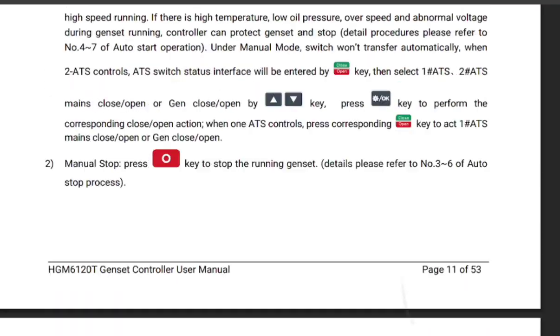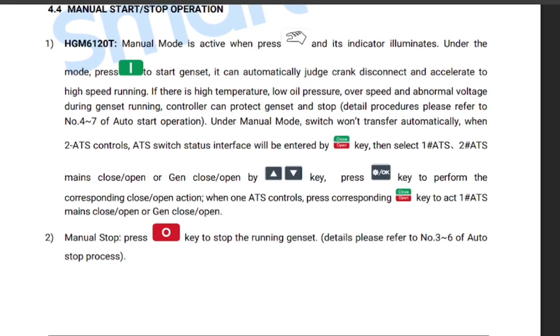So as you can see, here are some setups. As you can see, HGM 6120T manual mode is active when you press the hand key, and its indication illuminates under the mode. Press the green button, the I button, to start the genset. It automatically judges the crank disconnect and accelerates to high speed running. If there is a high temperature, low oil pressure, over speed or abnormal voltage during the genset running, the controller can protect the genset and stop.